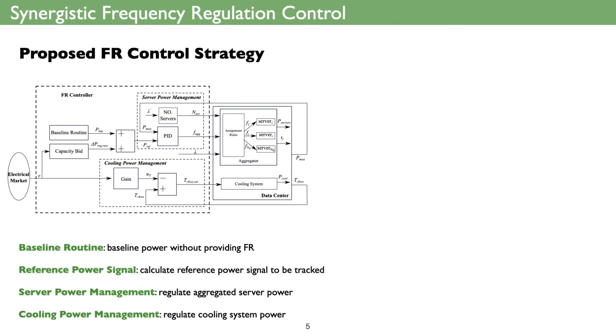So in data centers, to enable a data center to track a frequency regulation signal, we have to have a frequency regulation control. In this section, we propose the synergistic FR control strategy for data centers. The schematic is shown in this slide. It consists of four parts. Baseline routine. In this baseline routine, we calculate the baseline power of the data center when it's not used to provide FR. And then we will use the baseline power to calculate the reference power signal that the data center should follow when providing FR.